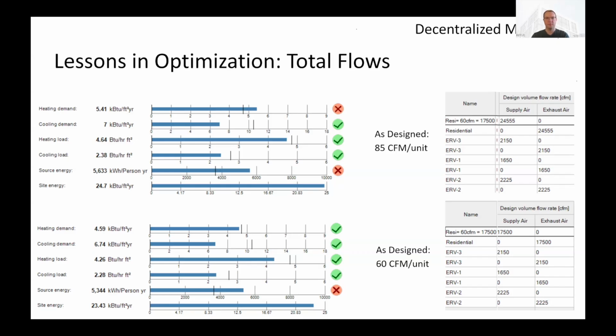And then using 5 air changes per hour for a kitchen, they came up with, yeah, most of our units are going to be 60 CFM. So they go 25 for a bathroom, 60 for a kitchen, we get 85 per unit. The other thing to note is that this project has almost an infinite amount of different units. There are 280 plus units overall, and I bet there are 40 or 50 different actual unit configurations, maybe more. There are some setbacks, different plans, and most of these are practically custom.